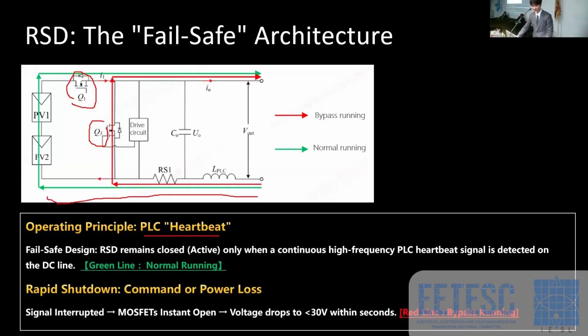Okay, let me repeat again. The green line is normal running. Whenever the heartbeat signal is lost, it will change to bypass running. So Q1 will open immediately, Q3 will close immediately, and the rapid shutdown will cut the PV panels from the system. That's why the high voltage will decrease to such a low level.